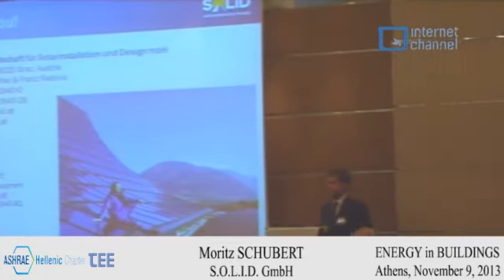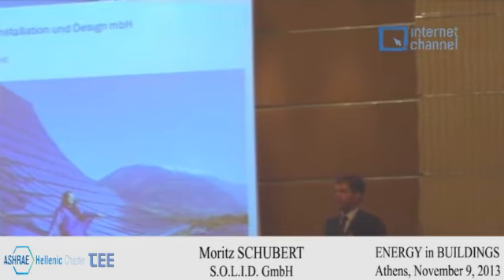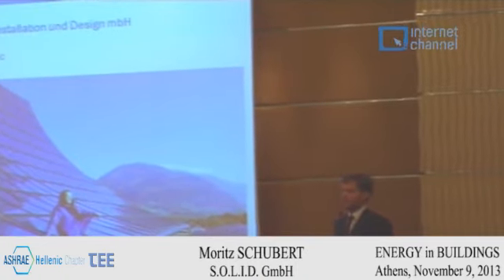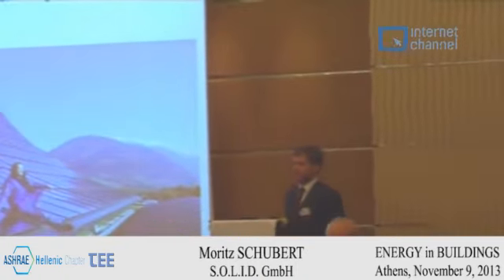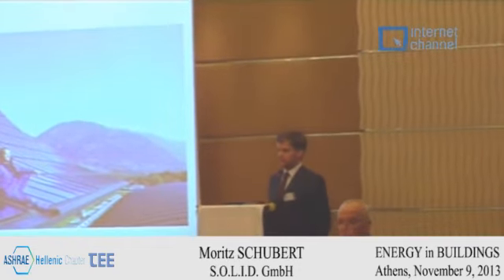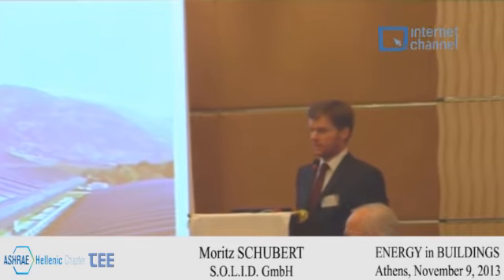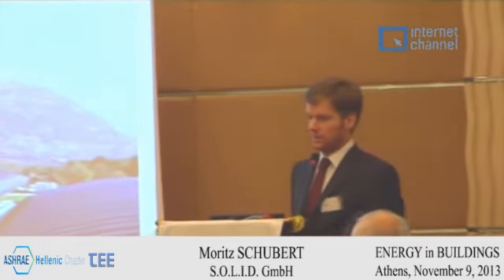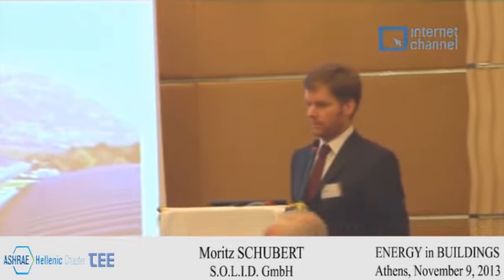For the cooling power, you can normally say the installation cost per kilowatt of cooling power is between 800 and 1,200 euro per kilowatt of cooling power installed.